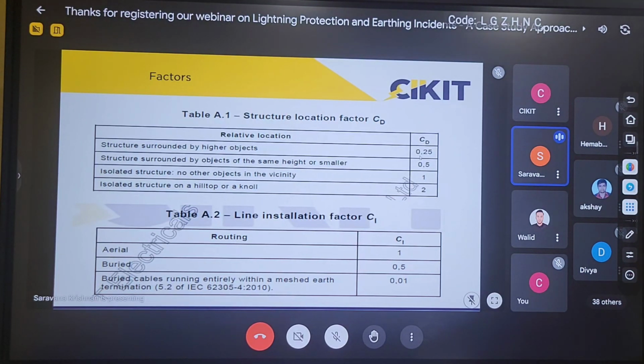The next one is the line installation factor. For example, if I take my building, for all the equipment I will be taking the power line from the outside. How am I taking this power line? If my power line is an overhead line, that is aerial, the probability of lightning directly striking the power line will be higher, and hence the risk is also higher. But if I am taking the power line through an underground cable, the effect of a direct lightning strike is lower, whereas if lightning strikes near this power line, induction may happen. That is the reason the value of C is lower if I am taking a buried conductor and higher if I am taking an aerial conductor.